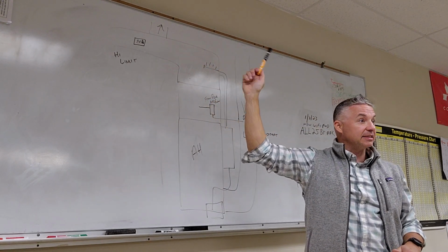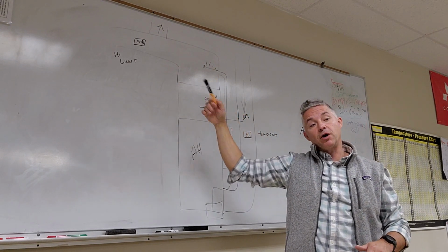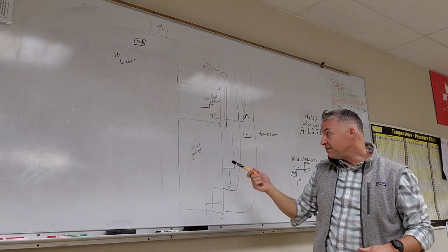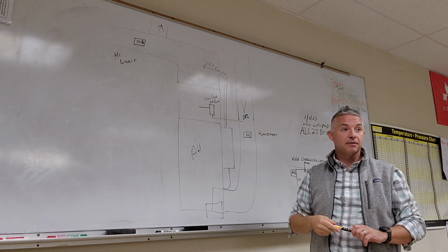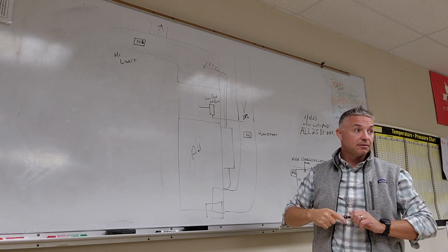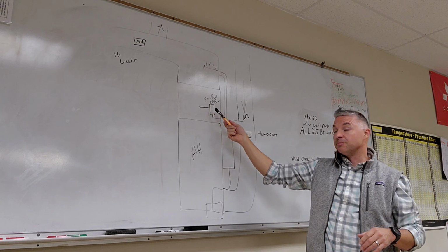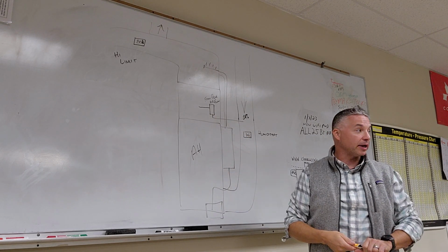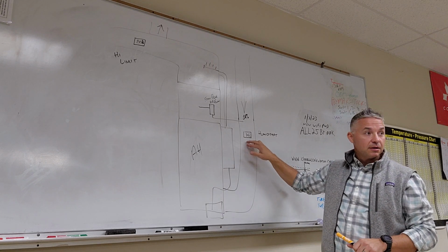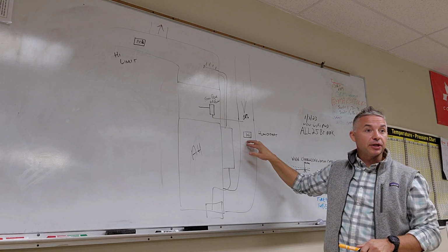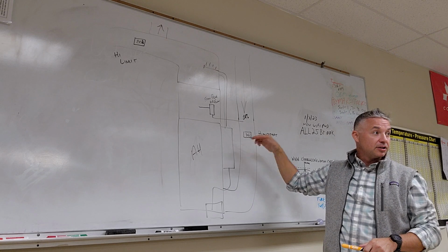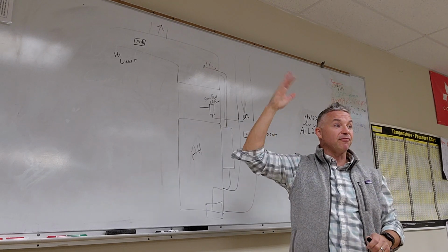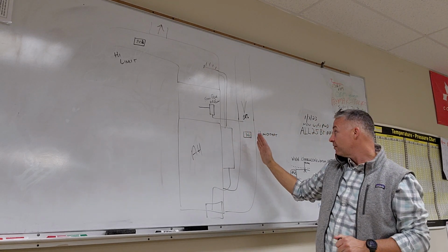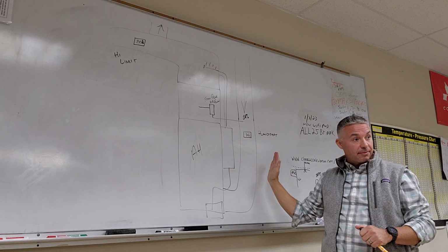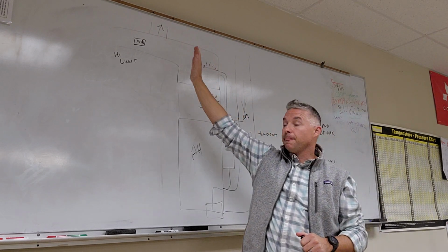So a high limit is a safety, okay? Every one of these is a safety, even the operating limit, because that's a low limit, right? If we didn't have that, then whenever the fan comes on, we would just have steam going and we'd have no low limit. We'd have nothing limiting how much steam we're putting into the system on the low side. So the house would just keep humidifying every time the fan came on, right?